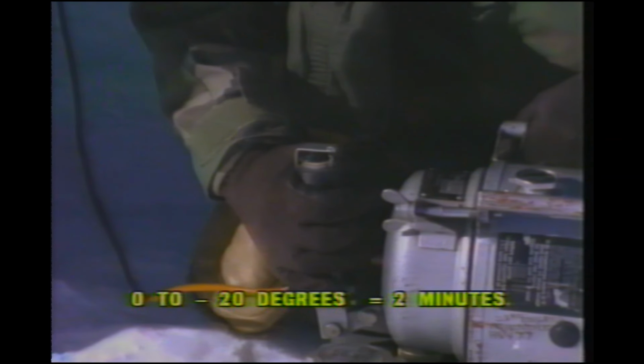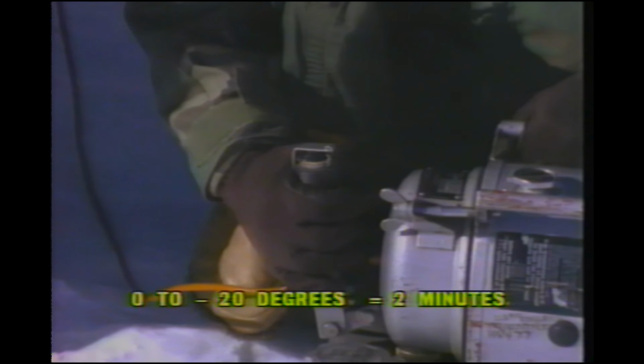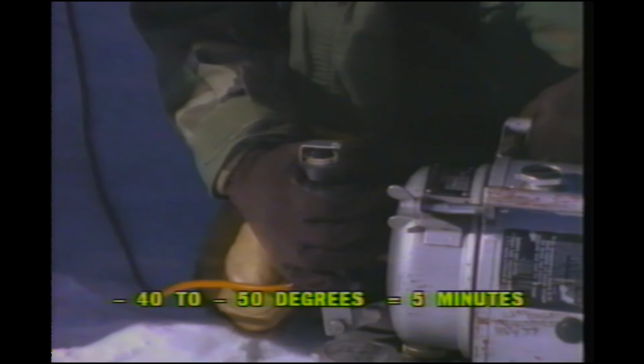If the temperature is 0 to minus 20 degrees Fahrenheit, hold the switch in for 2 minutes before pumping. Minus 20 to minus 30 degrees requires 3 minutes. Minus 30 to minus 40 takes 4 minutes. And in minus 40 to minus 50 degrees, the switch must be depressed for at least 5 minutes.